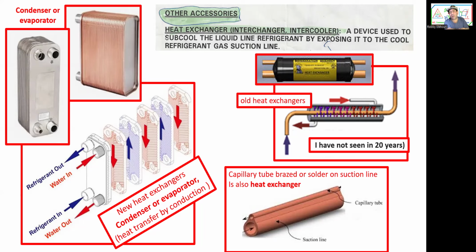But at the bottom, we also have the cap tube. The small cap tube is brazed around the suction line for heat exchange also. That's the heat exchanger. When we talk about heat exchanger, that's the heat exchanger. Pretty much anything that exchanges heat through conduction, because transfer through conduction is the best heat transfer. Remember from first class, conduction, radiation, and convection, right? The best heat transfer is conduction.